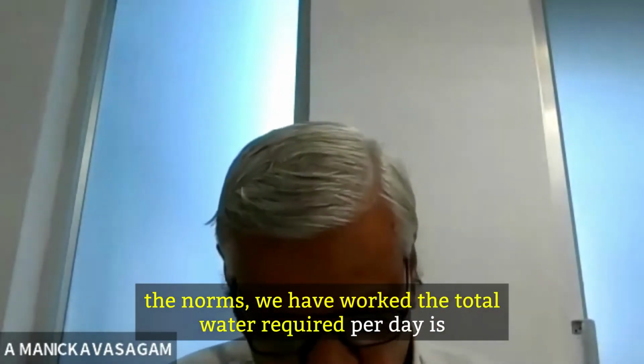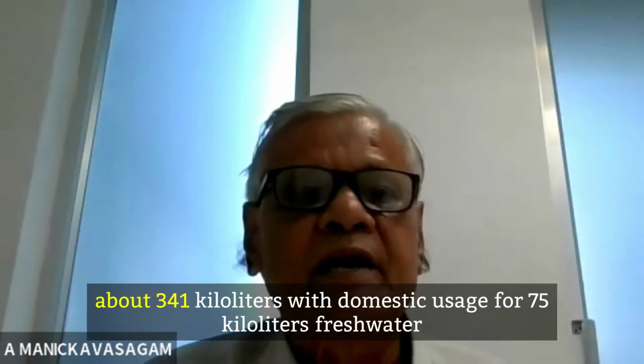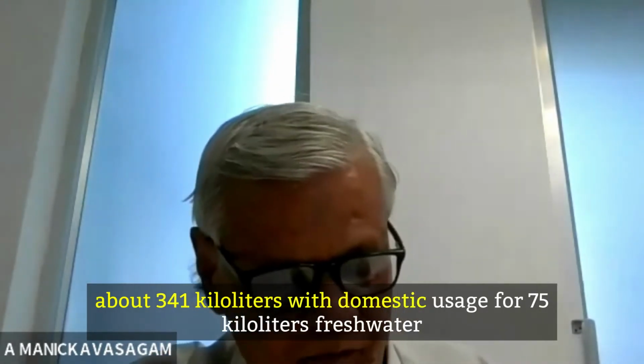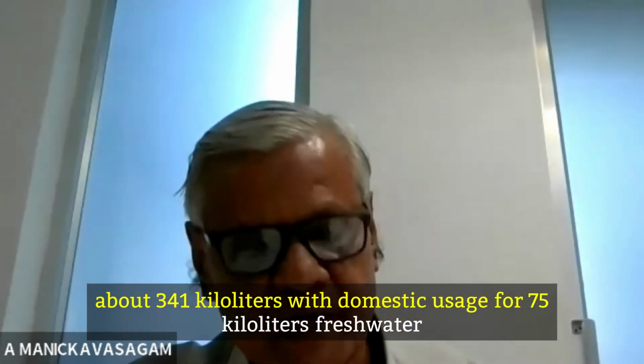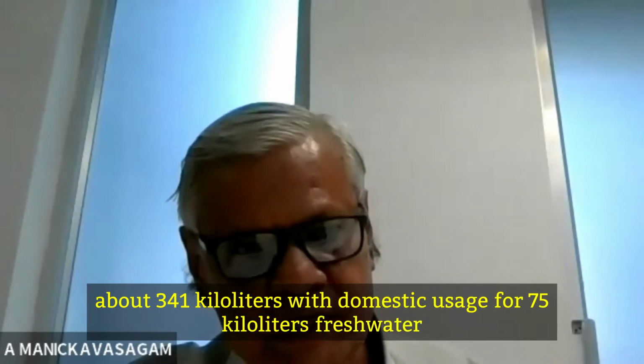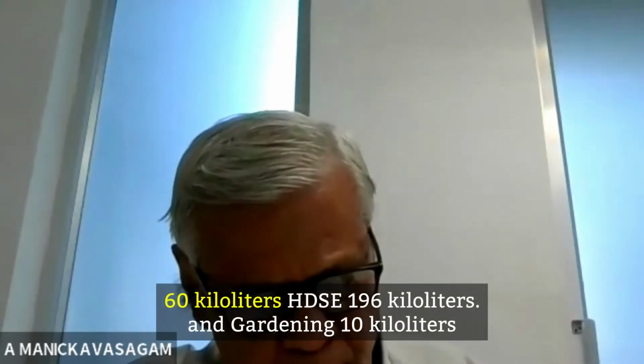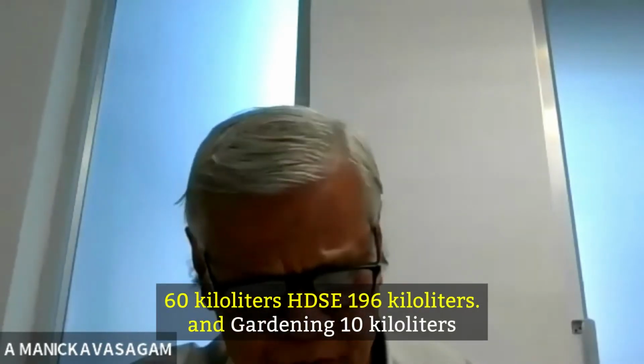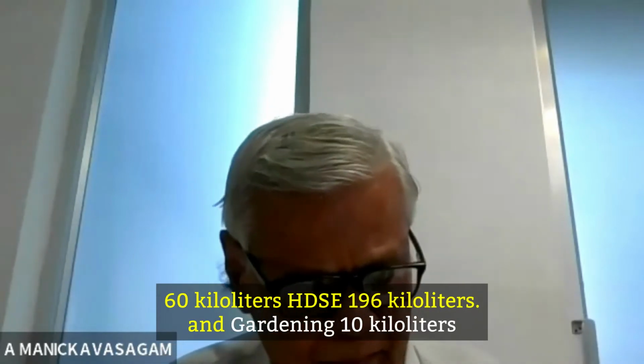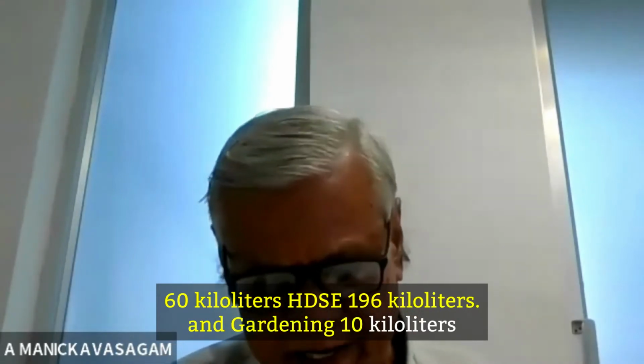The total water requirement per day will be about 341 kiloliters, with domestic usage at 75 kiloliters, flush water 60 kiloliters, HVAC 196 kiloliters, and gardening 10 KL.